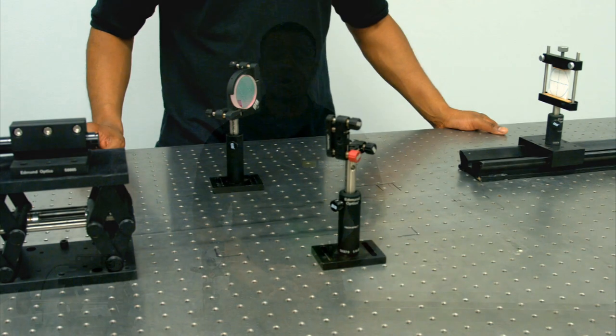In order to correctly align the laser beam, you have to use the first mirror to align the closer target position and the second mirror to align the farther target position.